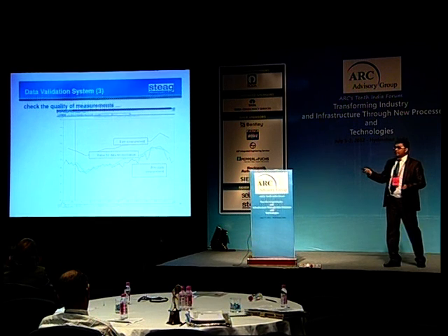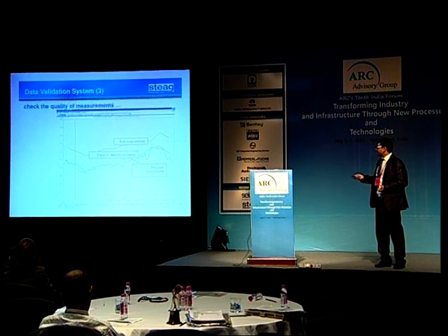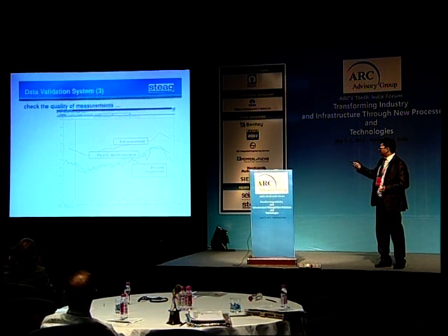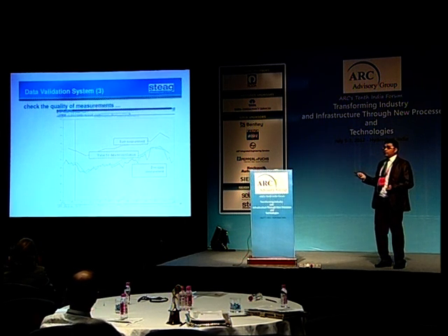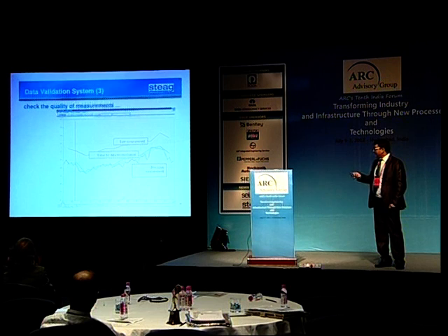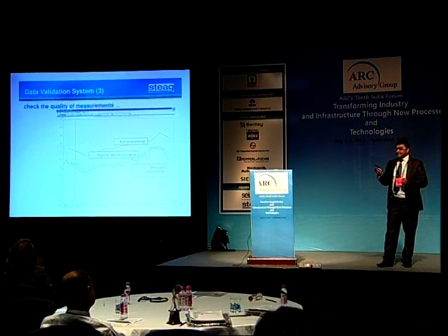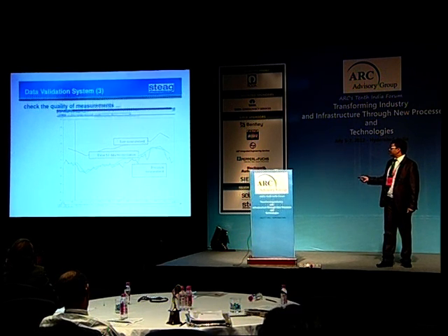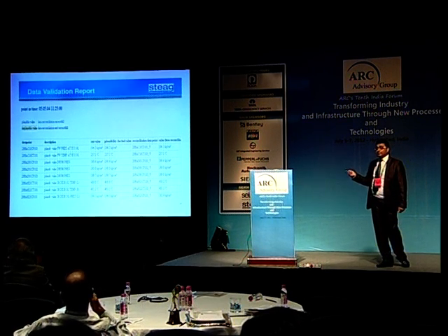And just one study we have done, on how accurate our data validation is, using these 3 layers of data validation which I just described. If you look at the line below, the green and the blue, the data reconciled value from Pardo and the precision measurements, if you put them for one instrument, they match very close to each other. That shows that it really improves the measurement of the power plants. So these are the kind of reports provided through Pardo in the data validation report.